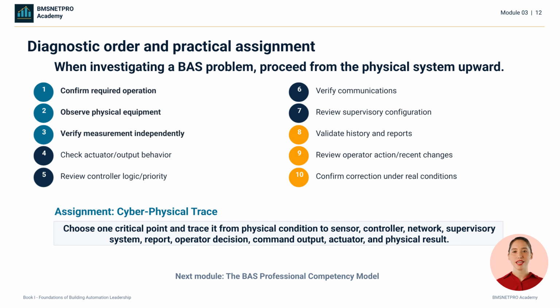The best practice diagnostic order starts from the physical process and moves upward. Confirm the required operating condition. Observe the actual equipment, verify the measurement independently, check actuator and output behavior, review controller logic and priority, verify communications, review supervisory configuration, validate history and reports, review operator action and recent changes, then confirm the correction under real operating conditions. For the practical assignment, choose one critical point and trace it from physical condition to digital information and back to physical output.